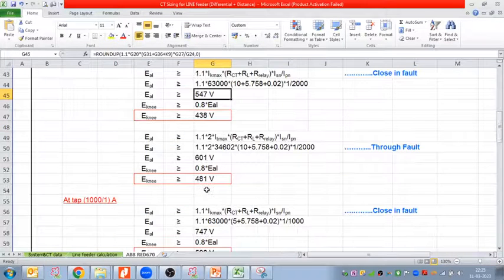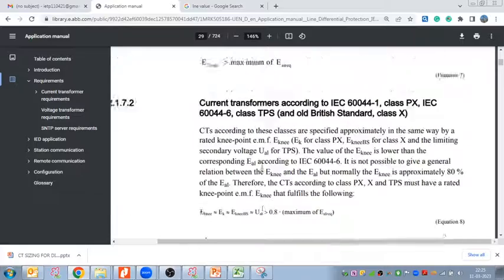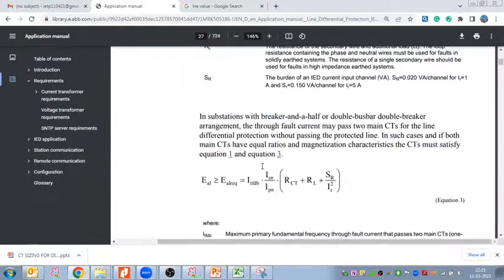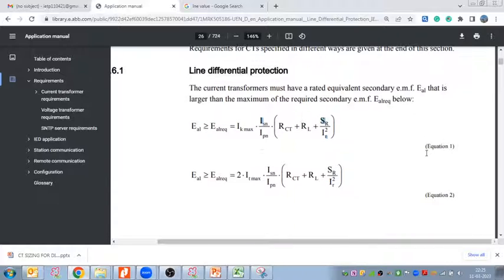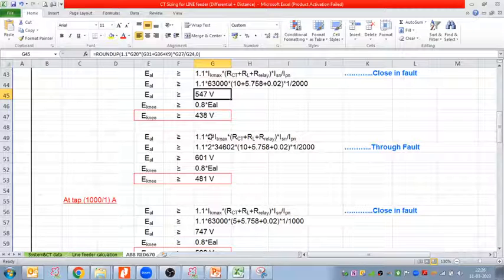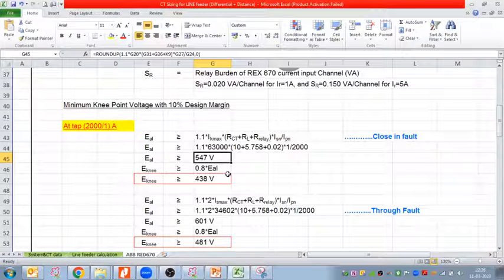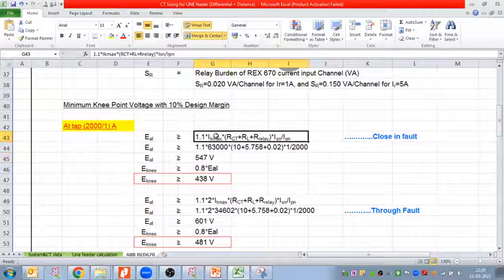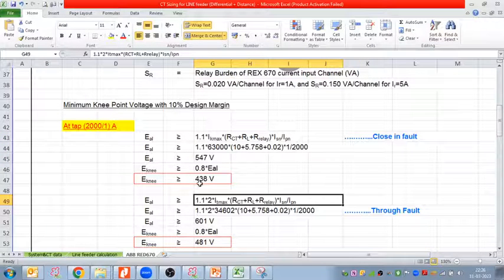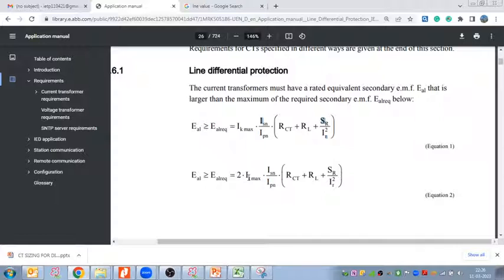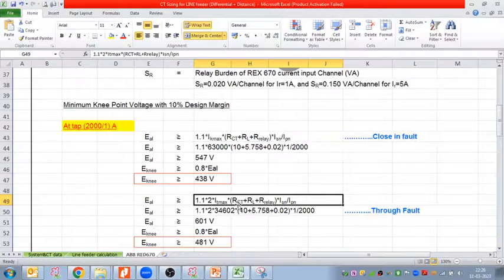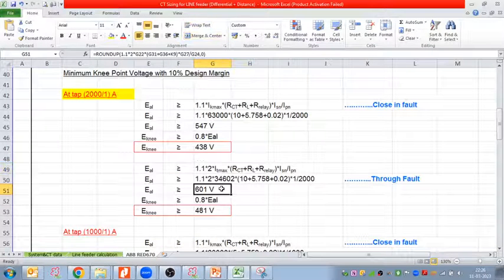Second case: now we have these equations for the through fault only. Now we need to solve equation number 2 also, which is for the through fault case. So again 2 into IT max, same things, but in this case you just need to change the fault current value, which is IK max, and now this is IT max, and 2 is given in the formula only. So 2 into IT max, so 2 into 34602 into this much as we have done here. This value is coming 601 voltage.